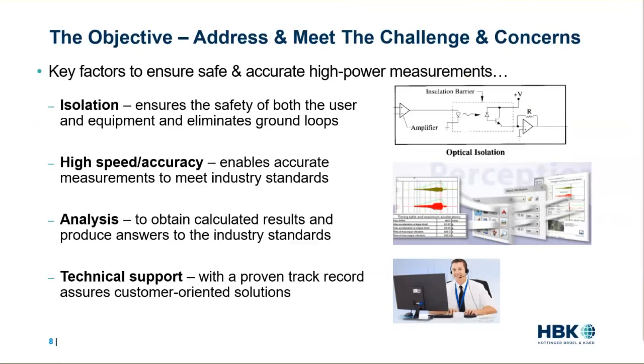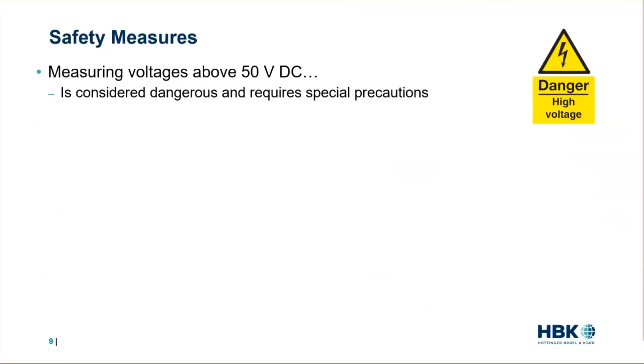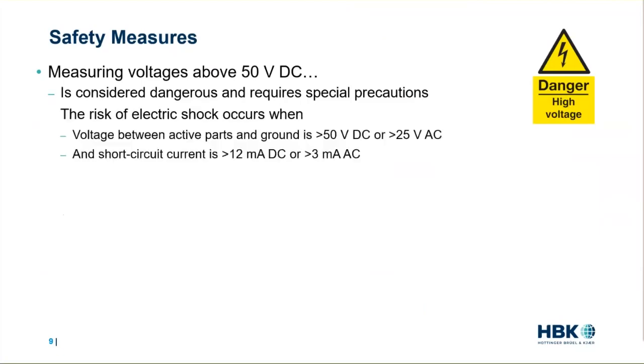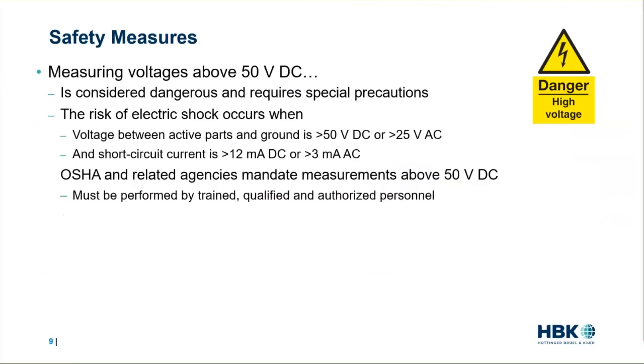Now, before we talk about these key factors in more detail, let's first talk about safety measures. In fact, we'll begin with the most important concern, safety. Some or most of this may seem obvious, but it's important enough to remind ourselves to be safety conscious and be aware of the danger involved. For example, measuring voltages above 50 volts DC is considered dangerous and requires special precautions. In fact, the risk of electric shock occurs when the voltage between active parts and ground is greater than 50 volts DC or greater than 25 volts AC, and short circuit current greater than 12 milliamps DC or greater than 3 milliamps AC. In fact, OSHA and other related agencies mandate measurements above 50 volts DC are to be performed by trained, qualified, and authorized personnel.